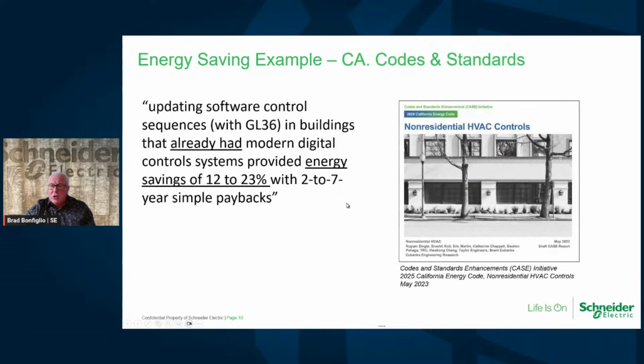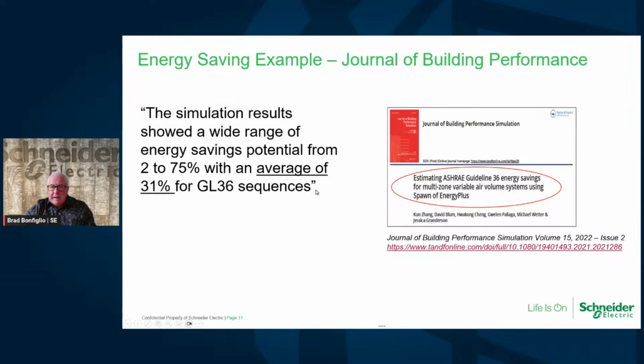Let's look at another one. Here's California codes and standards. This one was interesting because they looked at if the building already had a modern building management system, what would be the added benefit of adding Guideline 36 to either that system or a new one? They rated it as 12 to 23% energy savings. And again, this is assuming they already have a BMS in place. So I thought that was a really interesting one from California. And then the last one, Journal of Building Performance, their simulation they ran on it. Again, we don't have a lot of case studies out there yet because it's an evolving specification or guideline, excuse me, that is coming out. So a lot of these are actually simulations. In this case, they tried it with the average, the same results as what Berkeley came up with, 31% energy savings.